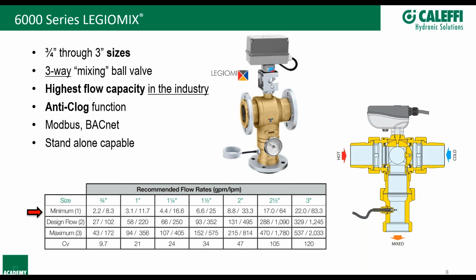One of our biggest demands for this valve when we first brought it to market was not specified design build type projects, and I was really surprised by that. It was those guys that have a building that's 30 years old and they've been replacing mixing valves every year, or gutting and cleaning mixing valves twice a year for the entire life of that building. They were just looking for something more robust that can handle harsh water conditions without having to be maintained as regularly and have all the issues that some of the thermostatics will have. On top of that, a ball valve gives incredible flow rates with really low pressure drops. So when you talk about sizing the valve, you're getting the best bang for your buck out of this valve as long as it's sized appropriately, for sure.